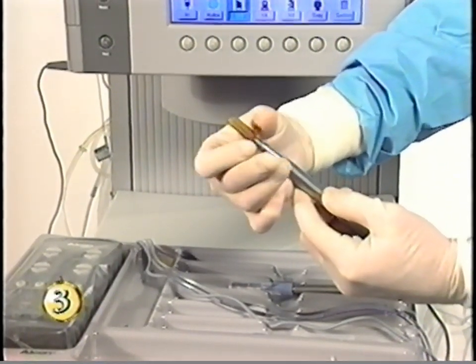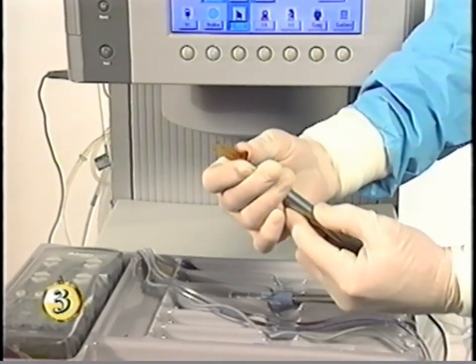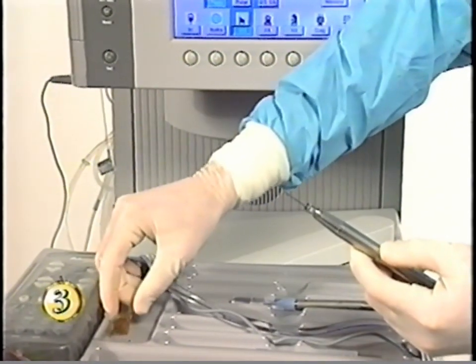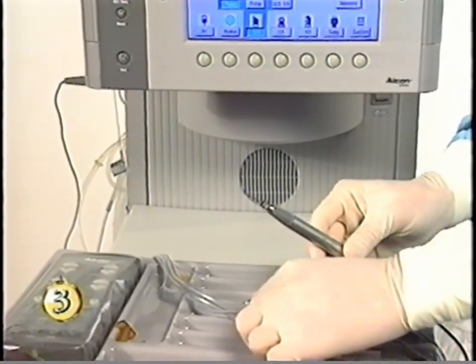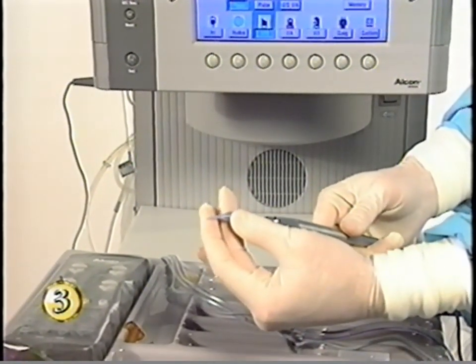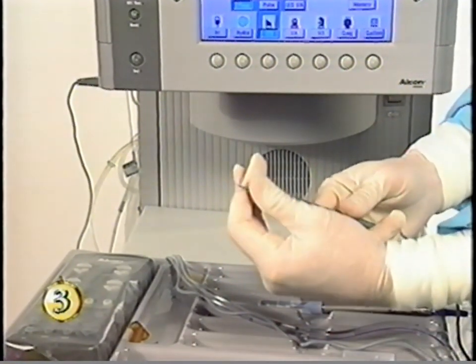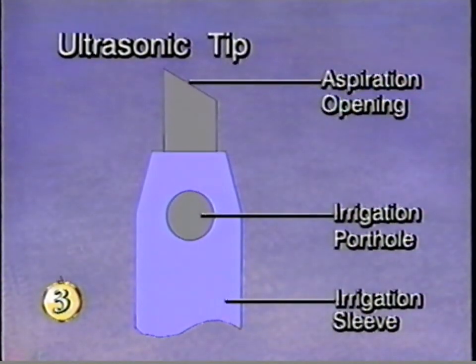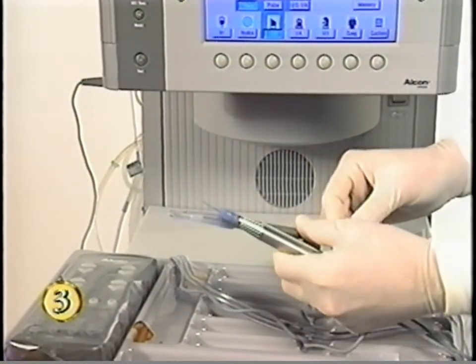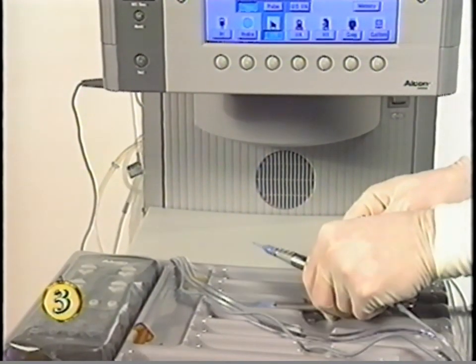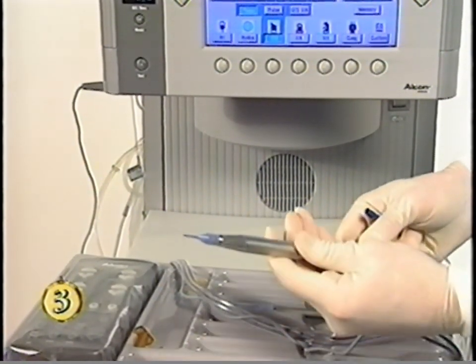Keep the wrench handy to remove the tip after surgery, but do not use the wrench in subsequent cases. Fit the Turbosonics infusion sleeve with bubble suppression insert over the tip. This diagram shows the optimal alignment of the sleeve to the tip. Remove the tubing from the IA handpiece and connect the irrigation and aspiration lines to the ultrasonic handpiece.